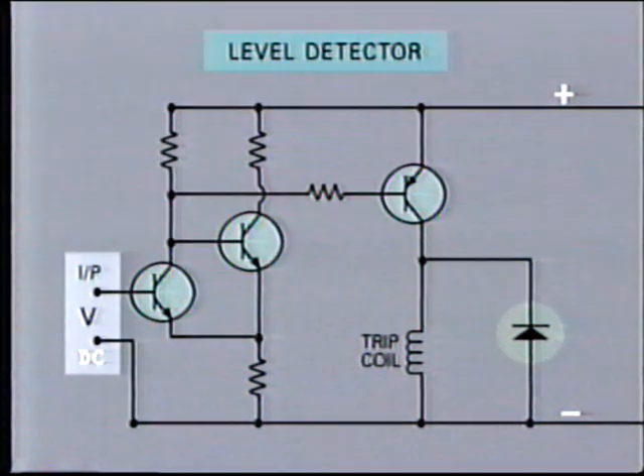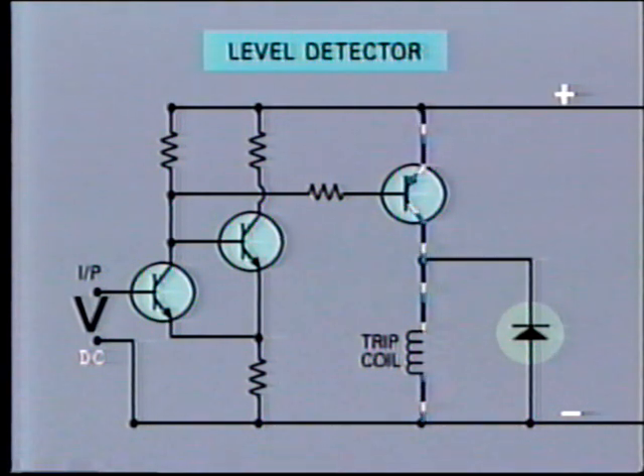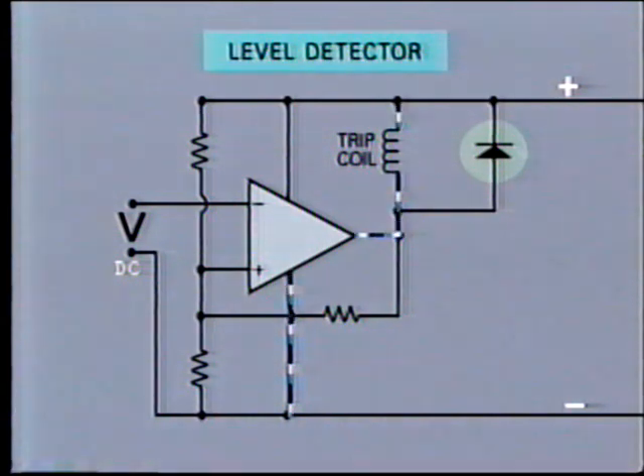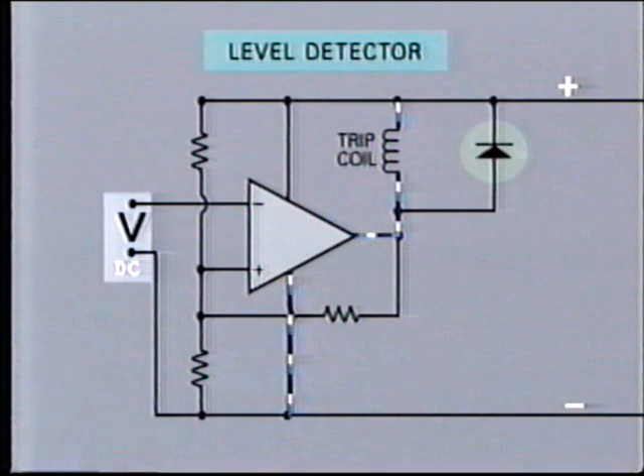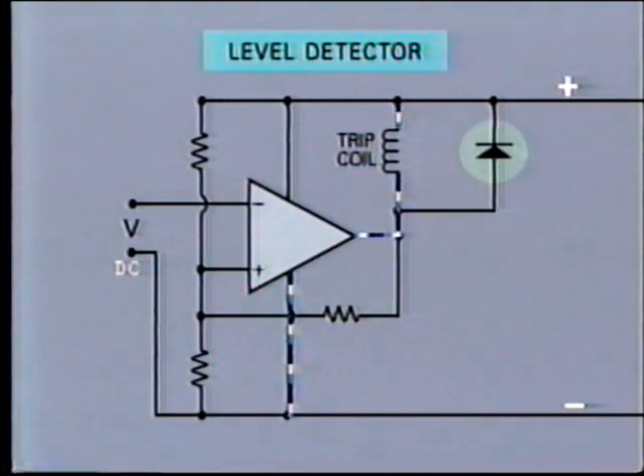The input signal is rectified to a DC voltage, and when this level exceeds the preset point, the output is switched on, and a relatively large current flows through the operating coil, which initiates action. The equivalent circuit using an IC chip is shown here. You'll recognize the operational amplifier. In both of these arrangements, as the input signal level decreases, the point is reached when the relay resets and is again ready for operation.